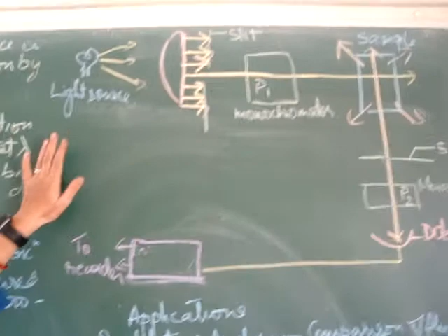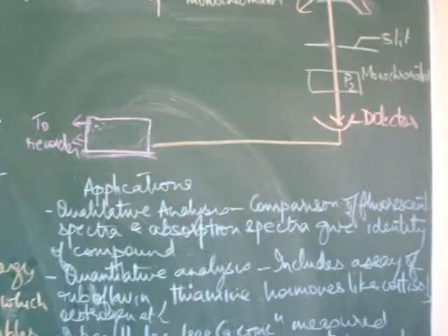Here is the flow diagram. This is the light source, this is the collimating device and choosing the wavelength. Monochromator P1 is present, it will choose a wavelength with which the sample has to be irradiated. The second monochromator is kept at right angles because emission takes place in all directions, while transmittance takes place in a straight line. That's why the second monochromator is kept here. It chooses the wavelength which the sample emits maximally, and by that the concentration of the substance is detected by the detector, which is then sent to the recorder.